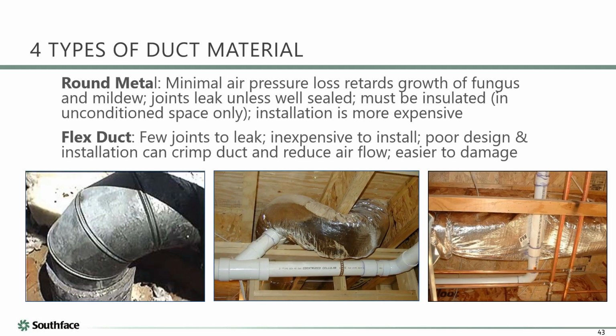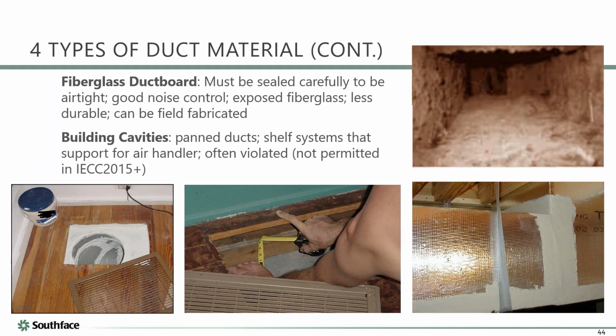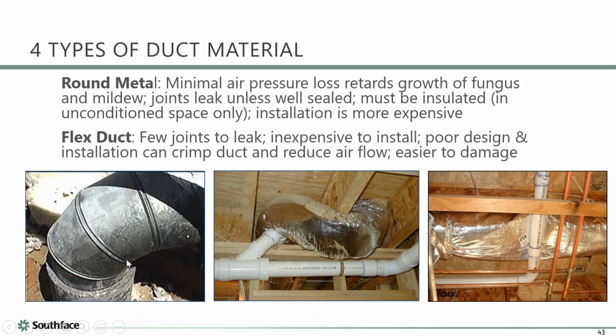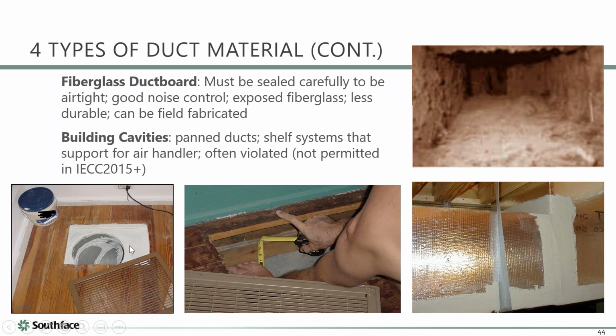So what materials can we use? There's really 4 types of duct materials. There is metal ductwork. Round metal, there's also square or rectangular metal. Metal duct, you know, certainly has some good advantages. It's very durable. It's also very expensive. Flex duct, which has probably replaced it, has some advantages, but also you probably wouldn't be doing this with metal duct, what you see in these 2 pictures. There's also duct board, fiberglass duct board, which has the silver lining on the outside. It's interesting, that's the pressure barrier. That's where you want to have the sealant, on the outside of duct board, but on flex and metal ductwork, you want the sealant to be on the inside. So we'll talk more about that.